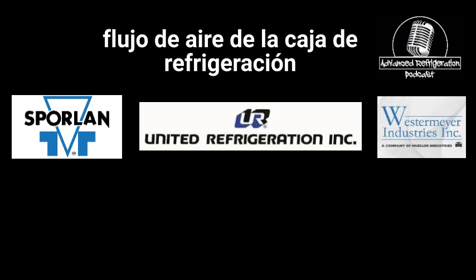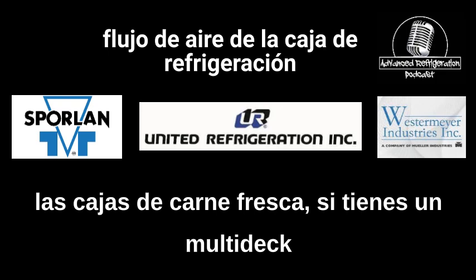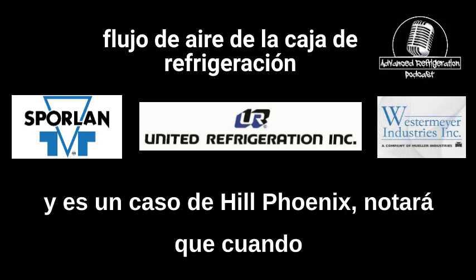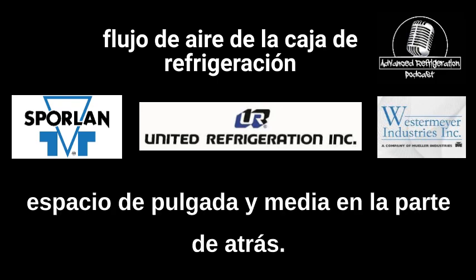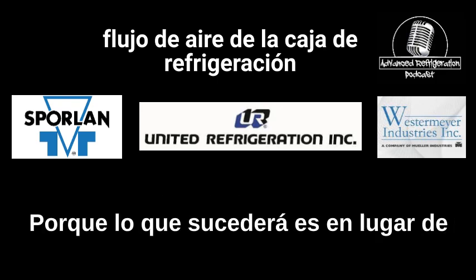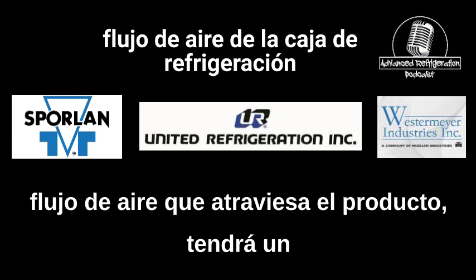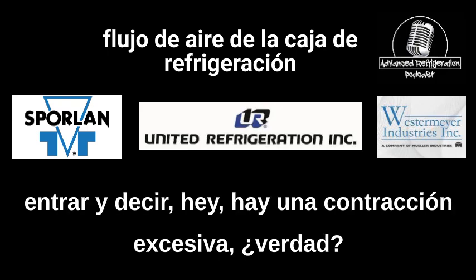I don't know. Maybe. Also, in a lot of these fresh meat cases, if you have a multi-deck and it's a Hill Phoenix case, you'll notice that when the shelf is at an angle, there's usually about a 1.5 inch gap in the back there. They sell shelf extenders to cover that gap, because instead of the airflow going across the product, you'll get a call where the customer says, hey, there's excessive shrink.